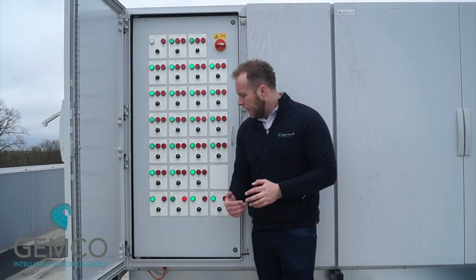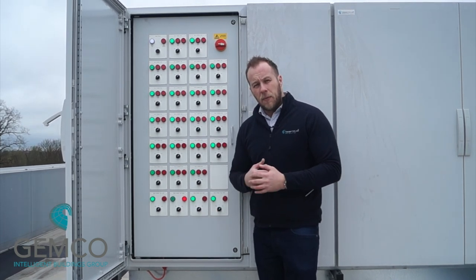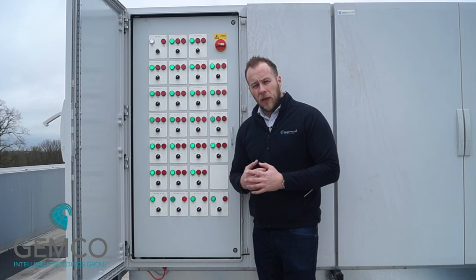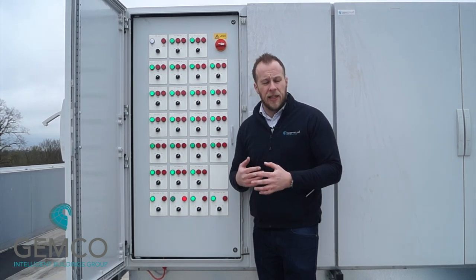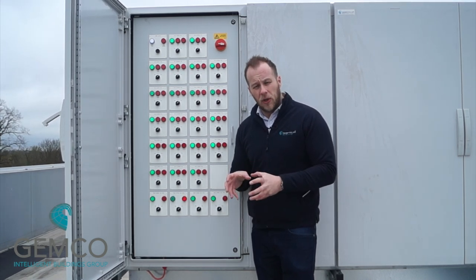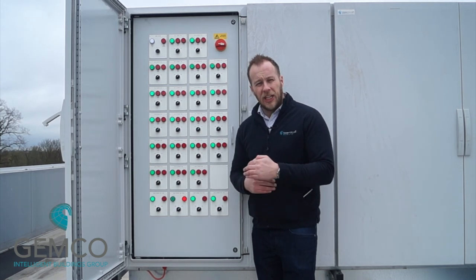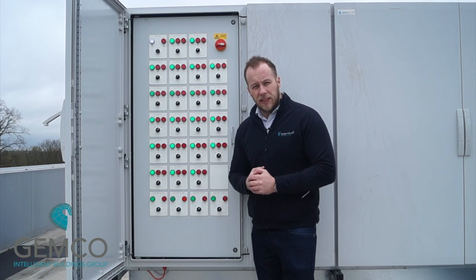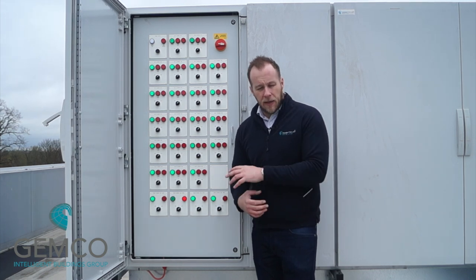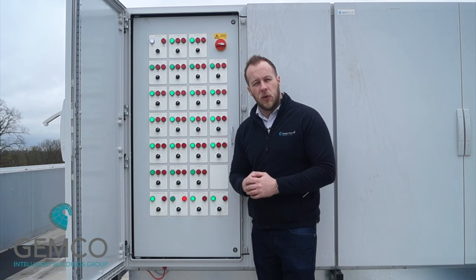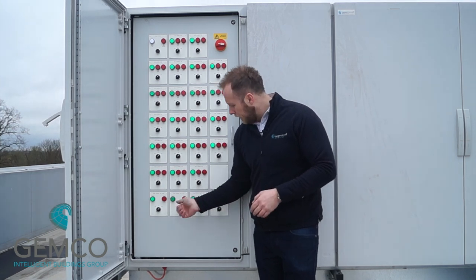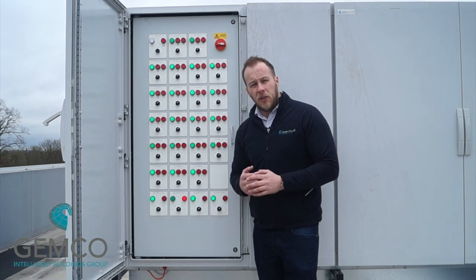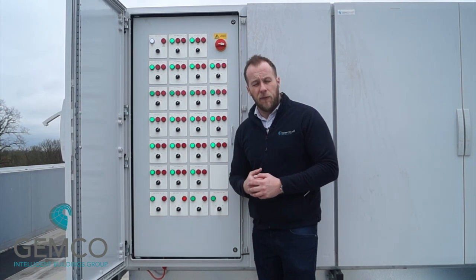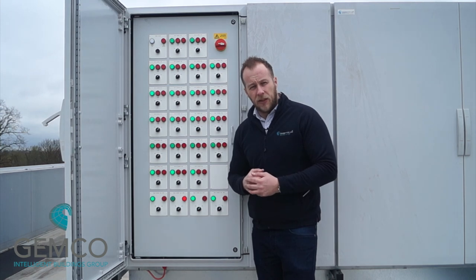Now the toilet extract fans, there's four of them, they're enabled on their own time switch, and once they're enabled they run under the dictates of their own little smart controller. There's an Eco Smart controller in each of them, and they'll do their own duty changeover if there's no flow established across the duty fan. The BMS does not do the duty changeover of the toilet fans. So if a fault comes up on one of the toilet extract fans, you'll need to go to the unit that's showing a fault and press the reset button on the Eco Smart controller.